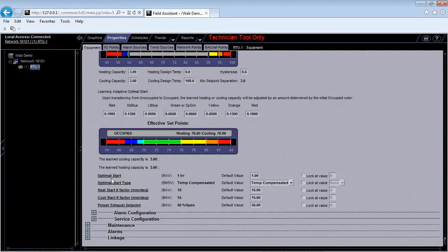You kind of want to leave it how it is. One thing to look at would be optimal start. Okay. Optimal start is a feature that comes standard on all Carrier controllers, and what it is, it's a calculation for how long it takes the unit to reach its occupied set points once it actually goes into occupied mode. So when I switch from unoccupied to occupied at 6 a.m., my unit is going to start calculating at that time how long it takes to get the space temperature back up to its set point. And once it does that, it uses that value and it learns and tries to start the unit a little bit later. So it's a built-in energy saver, so you don't actually have to start the unit 2 hours before to guarantee you're back to the space temperature.